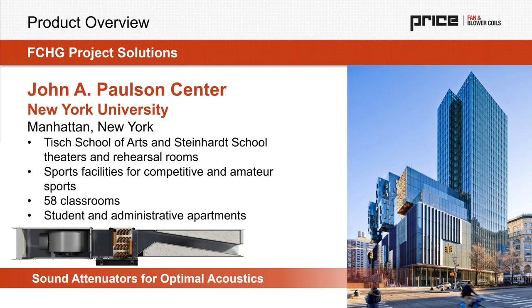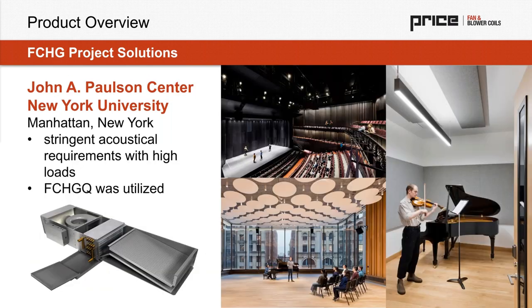A sound attenuator is cataloged and tested to ASTM E477, and that silencer standard actually requires 5 equivalent duct diameters of straight duct upstream and 10 equivalent duct diameters of straight duct downstream to catalog performance. In this case, we actually integrated it into the fan coil and tested it as a solution, which means you don't need to manage install conditions in straight duct as a design engineer. You can just mount it as a fan coil and know that it will be quiet even with non-ideal entering conditions and system effect. And so this product was used for theater spaces.